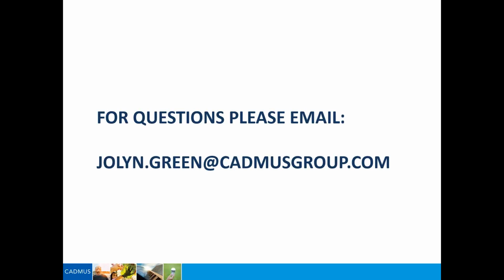The other question, and I've seen this before, is that a lot of times the code uses the word functional testing for lighting controls, but Howard used the word commissioning, which is kind of the same thing. A lot of times you can't actually get these systems set up properly until after the building is occupied, because the occupant brings in furniture and you don't know colors and things like that in the space. So this actually happens after certificate of occupancy.